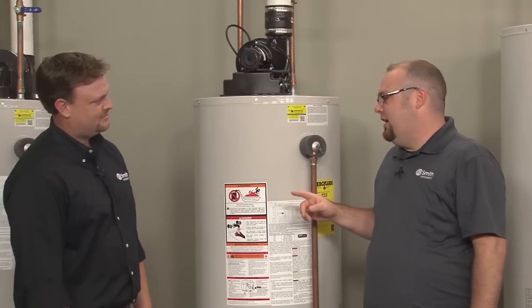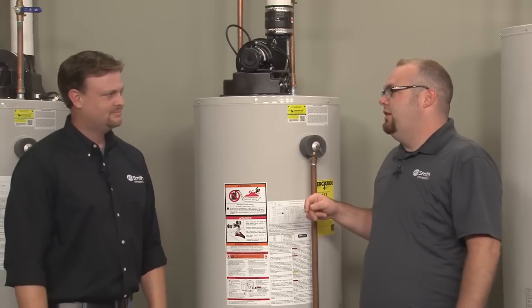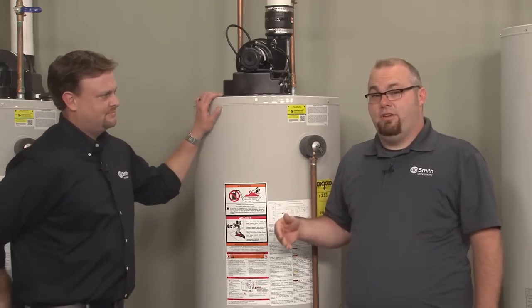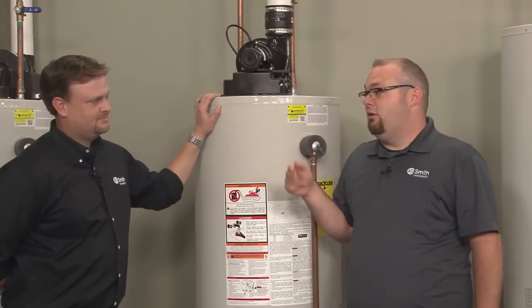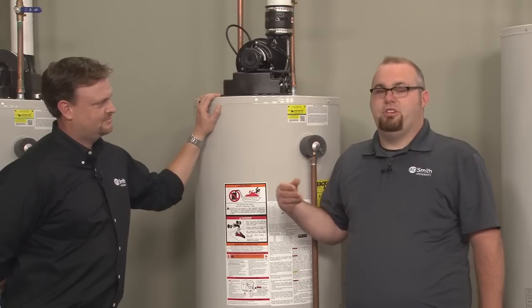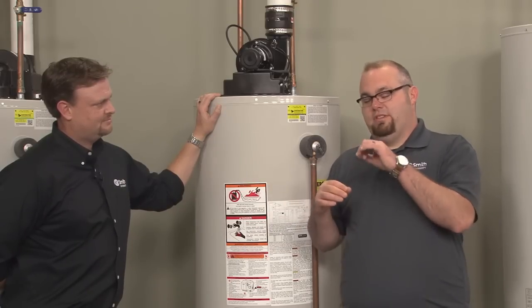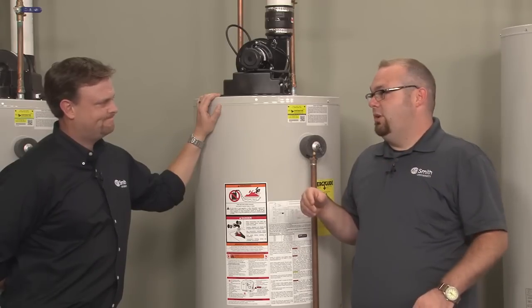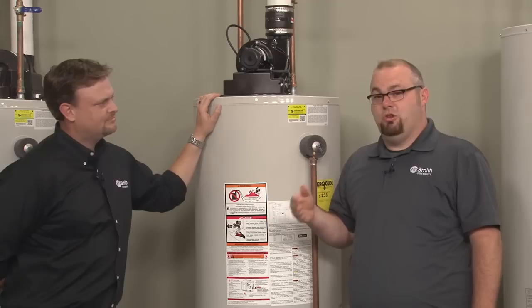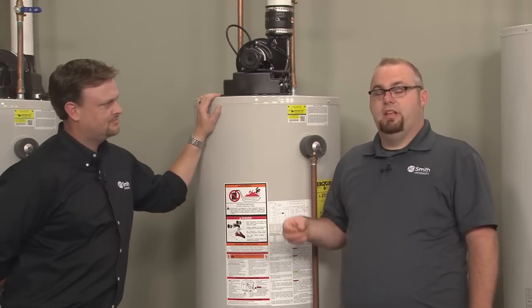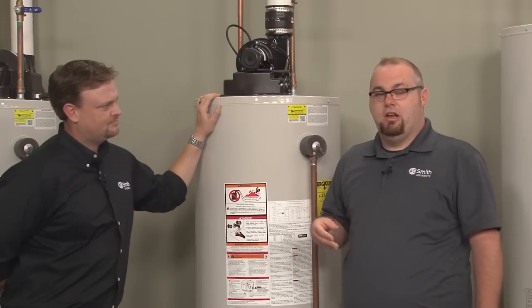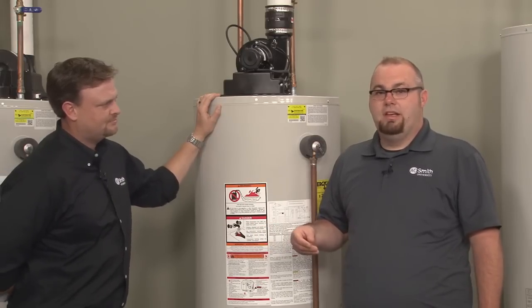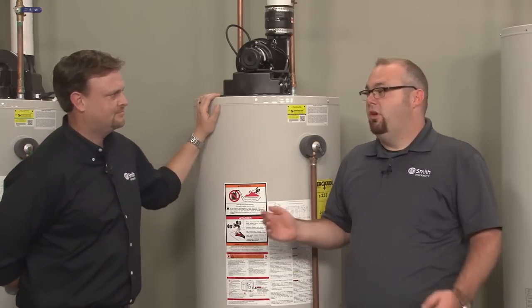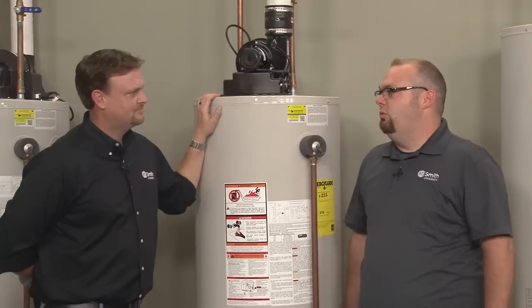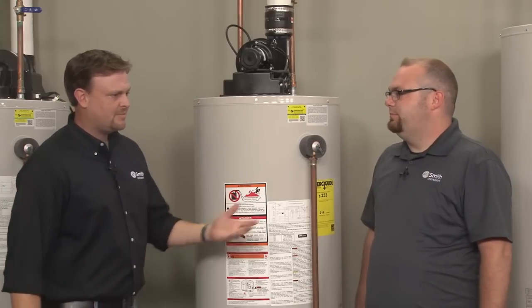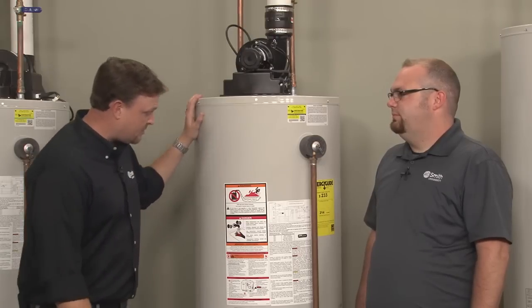And I will add one other thing that we didn't talk about, since we're talking about two heaters at once: if the blower doesn't start on an IntelliVent water heater, you actually have to check power going to the blower. You have a 6-pin connector that plugs into the junction box on the blower. You check between the two center pins, which is 2 and 5, and you should have 120 volts. If you have 120 volts and the blower doesn't start, the blower is bad. If you don't have 120 volts, typically that issue is going to be in the control valve. So just to add that, I know it's kind of confusing to do two at once. Yeah, and I wish we had another heater here, but unfortunately we do have the .70 though.